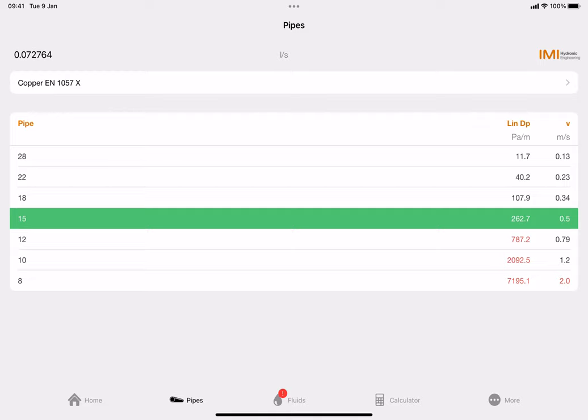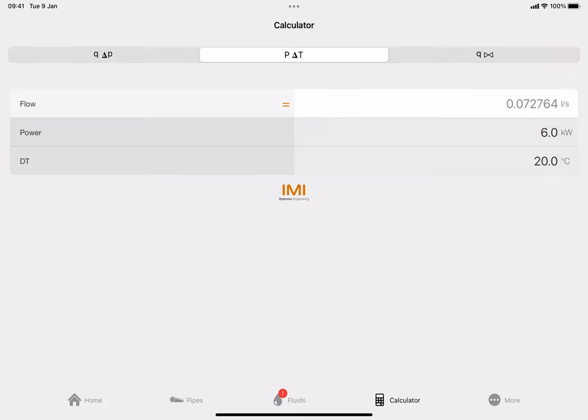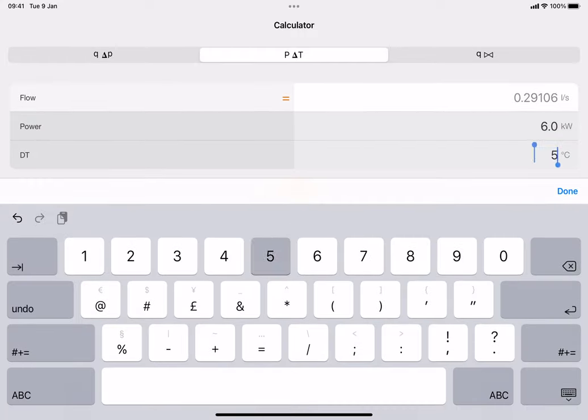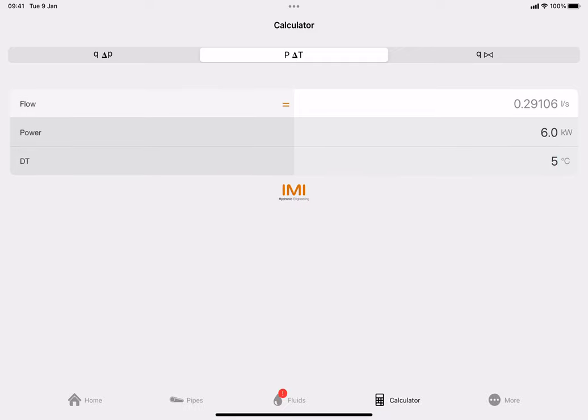Look at 22 millimeter pipe work: that gives us a pascals per meter drop of 40.2 and a velocity of 0.23 meters per second - really not a lot. So could we use that existing primary pipe work for a heat pump? Let's go back to the calculator and change to Delta T 5 since heat pumps are generally around DT5. Click done, then click back on pipes.